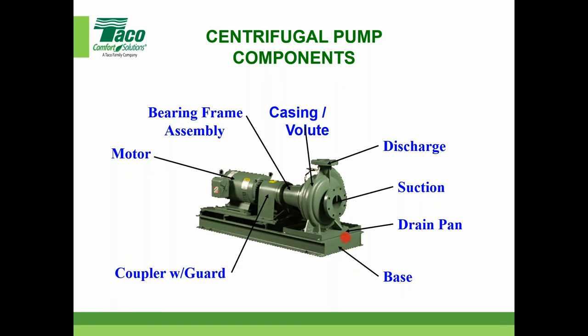A couple of things are important to realize about base mounted pumps, especially in HVAC. In different industries, some of the municipalities, different types of pumps, higher end pumps, you may not have to do this for base mounted pumps. It's right in the manuals. It's recommended that these are grouted. What that means is that cavity in there is filled up with a concrete grouting mix after the pump base is leveled and the pump itself is aligned. And we're going to talk about alignment as well. So that's just some advice there. Matter of fact, I'm going to go to our website very shortly after I'm done here on this screen, just to show you a couple of things in that regard.